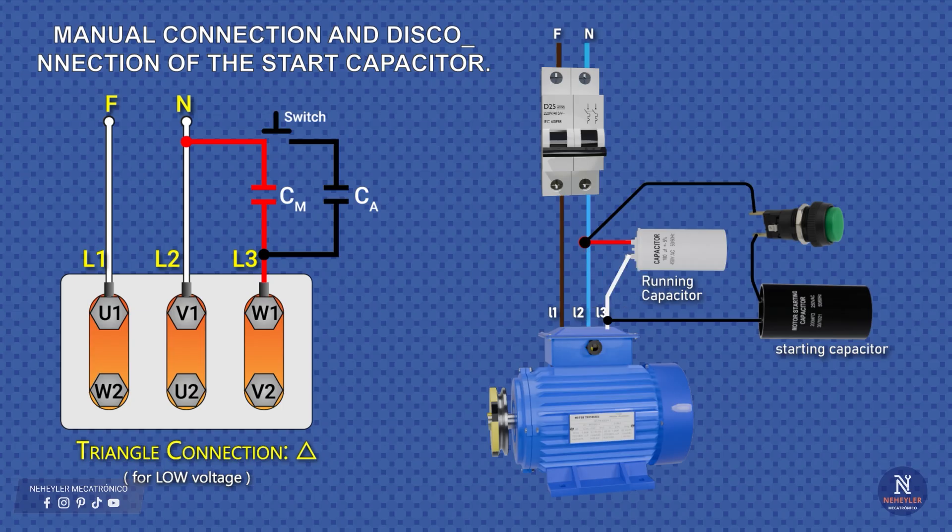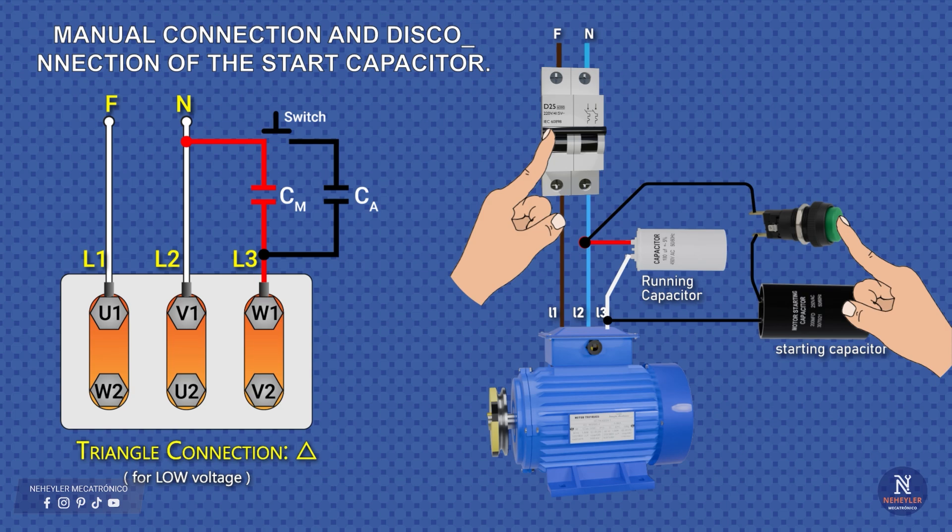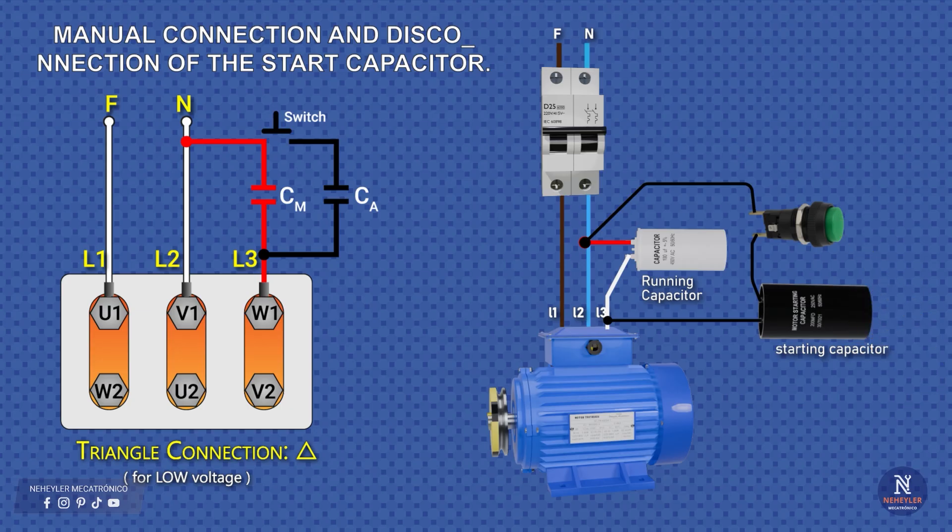How do we make it work? Very simple. With one hand we press the push button and with the other we turn on the circuit breaker. We keep the push button pressed for 3 to 5 seconds, until we hear that the motor has already reached its speed. Then we release the push button, and the motor continues running only with the run capacitor.